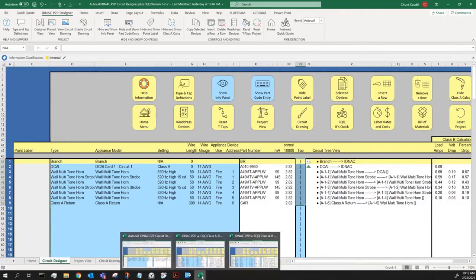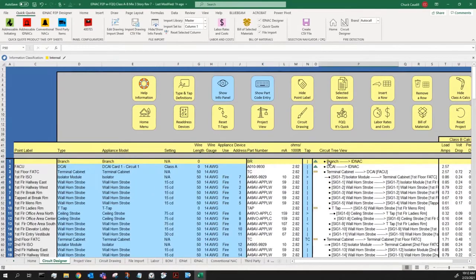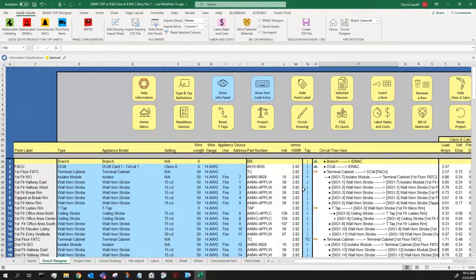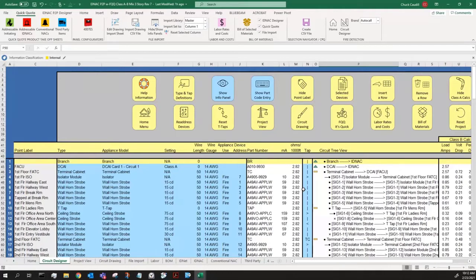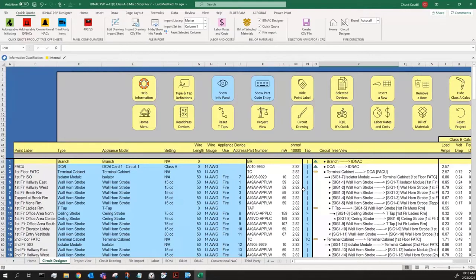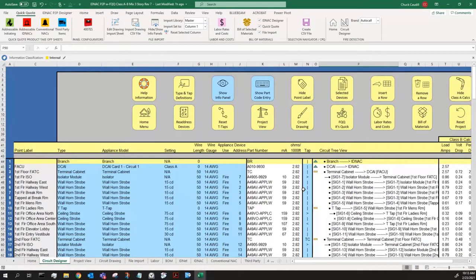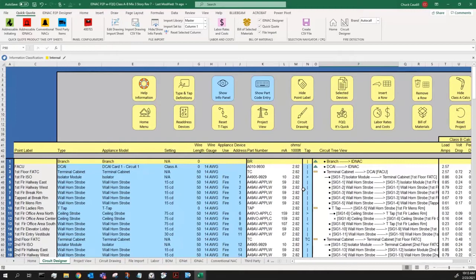So there are some exotic things you can do with these. Let's look at a Class A-B mix. So in this scenario, I'm going to take a three-story building. I'm going to run a Class A riser up from the first floor to the second floor terminal cabinet to the third floor terminal cabinet, and then a Class A return down. No devices on there yet. That is a Class A loop up and down. But at the floor levels, I'm going to run Class B devices there. And the only thing I should make sure and do is throw an isolator in as the very first device on each of the first floor, the second floor, and the third floor, and tap those off so you have a Class B loop that's tapped off that Class A riser. And if I get a short circuit anywhere on the first floor, the isolator will shut off the field wiring and I won't damage or jeopardize the rest of the loop.